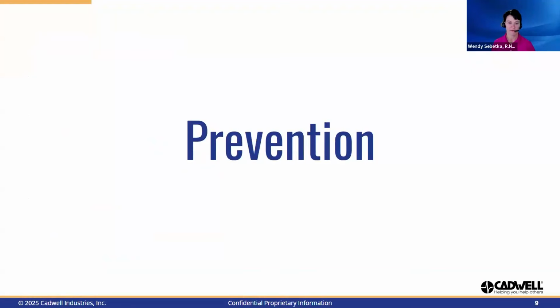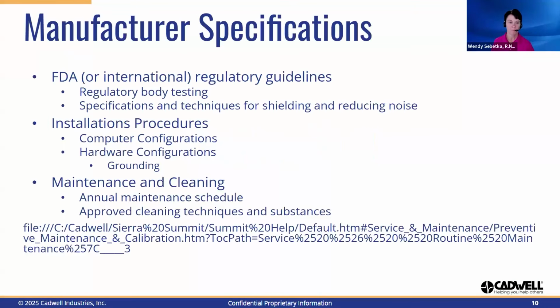Prevention. So how do we prevent the noise? All systems are required to follow FDA or international regulatory guidelines during the development process. These guidelines include regulatory body testing, specifications, and recommended techniques for shielding and reducing noise. Special consideration goes into ensuring shielding techniques are used during the amplifier and cable design process to allow external signals to be blocked or filtered out.